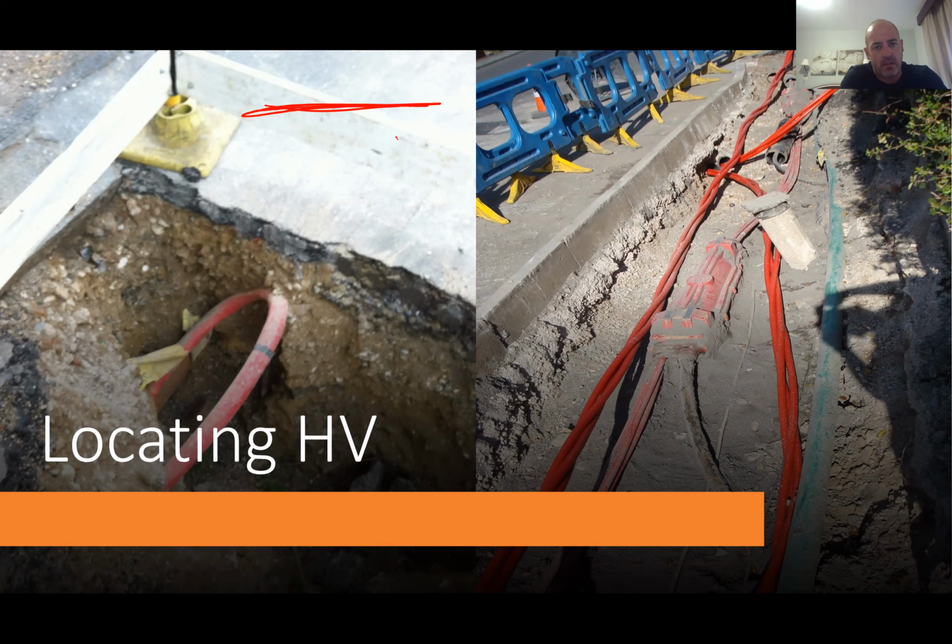What you might have is the LV cable kind of here and the HV here. And as we said, this has got a stronger signal on it, so this kind of gets masked by it. And again, before anybody starts shouting nulling out, it's an option we can come to later, but let's look at other things to consider. So these are some of the problems with it.